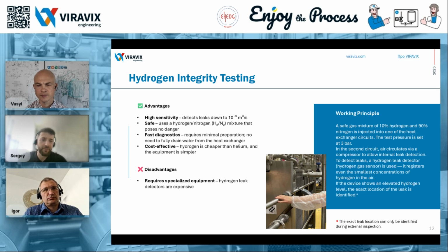And when we need to check for external leaks, we simply fill both sections with gas at the same time and then use the leak detector to locate any leaks from the outside. Among the advantages, it offers high precision, capable of detecting even microcracks at levels of 10 to the -6. It's also safe because the gas mixture used is hydrogen combined with nitrogen, which is non-explosive and poses no danger. Another benefit is the speed of diagnostics.